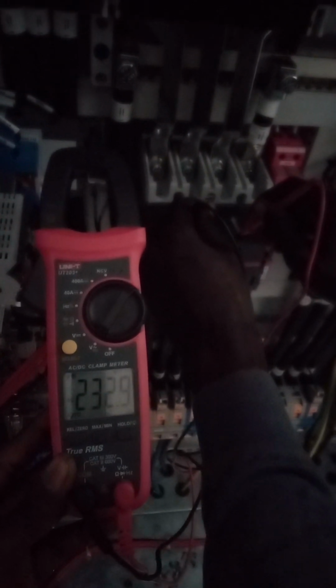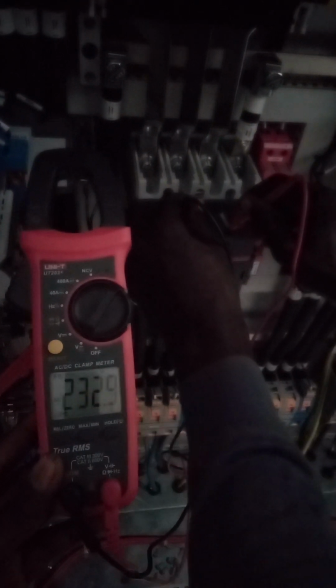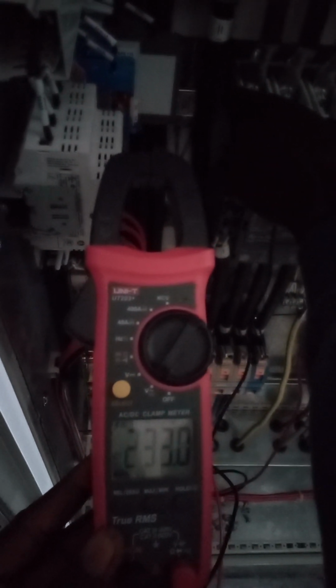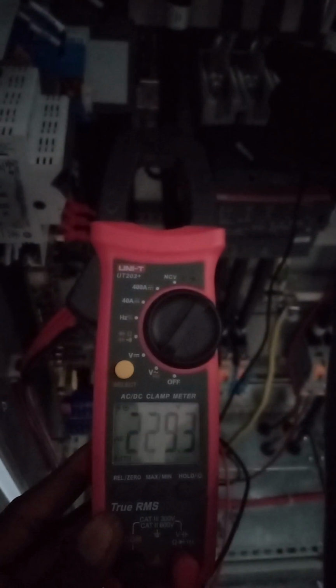And as we get up, we'll check at the coils of this contactor whether we do have power there. We realize that we have 232.9, as we can see. So we're having the coils of the contactor powered from the generator, meaning we are testing whether the contactor is on now. We realize, yes, 233.0 for line 1 and neutral, 228.8 for line 2 and neutral, and 229.3 for line 3 and neutral, implying that on this bus we do have power.